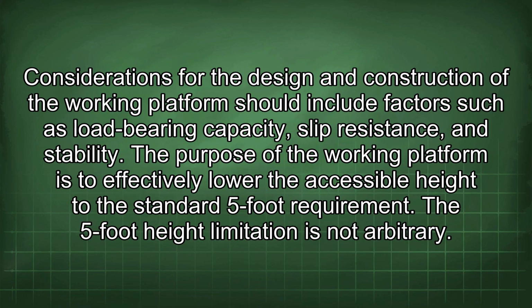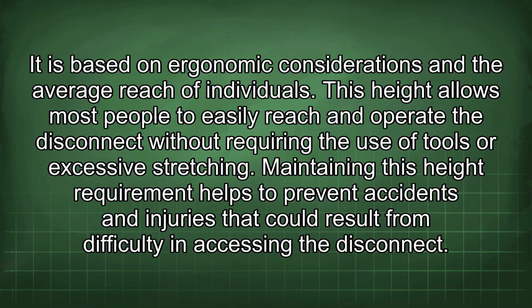Considerations for the design and construction of the working platform should include factors such as load-bearing capacity, slip resistance, and stability. The purpose of the working platform is to effectively lower the accessible height to the standard 5-foot requirement. The 5-foot height limitation is not arbitrary. It is based on ergonomic considerations and the average reach of individuals. This height allows most people to easily reach and operate the disconnect without requiring the use of tools or excessive stretching. Maintaining this height requirement helps to prevent accidents and injuries that could result from difficulty in accessing the disconnect.